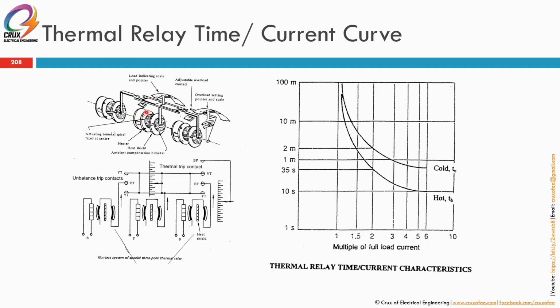So this is an example of the thermal relay time current curve. As you can see here, this is the bimetal overload relay. This is a very old relay. So there's a bimetal part here. Then this is the heater, these four squares here. Then red, yellow and blue will be coming directly from the CT. So the CT current will heat up this heater through the I squared R losses and will heat up the bimetal. So each of these bimetals, for each phase, will trigger the unbalance trip contact or the thermal trip contact of the relay.